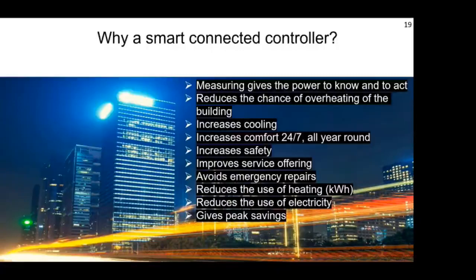These changes also have an impact on other aspects of the substation, giving reduced electricity usage for the pumps and the controllers. With inverters, the pump's not working as hard as possible, it's just ticking over, providing the heat that's required. The control valves are not opening fully. They may be opening a small percentage, just to allow a certain amount of heat through. All these actions will help give savings, which will be increased at peak times, making the whole substation more efficient. The system's being monitored 24 hours a day and it's only tweaking open, tweaking closed. If the heat is required, it opens; if it's not, it's shutting down. If you don't measure and monitor, you won't know what changes are needed to make the system perform better. So it's about understanding what is going on 24 hours a day, 365 days a year.